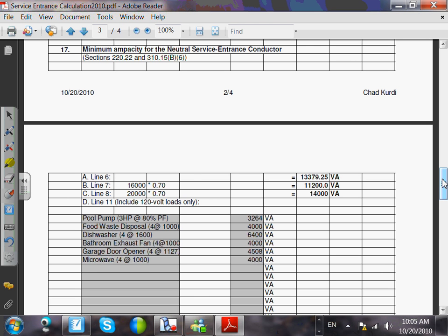For example, if this was a 200 amp panel bus-wise, and I decided to throw a 125 amp breaker ahead of it, this panel code-wise becomes a 125 amp panel. The main overcurrent protection device decides the code size of a panel.